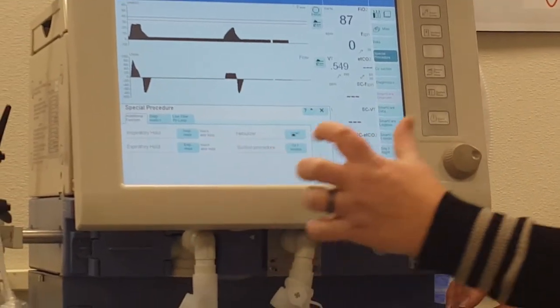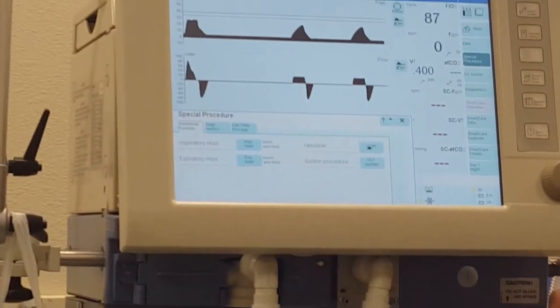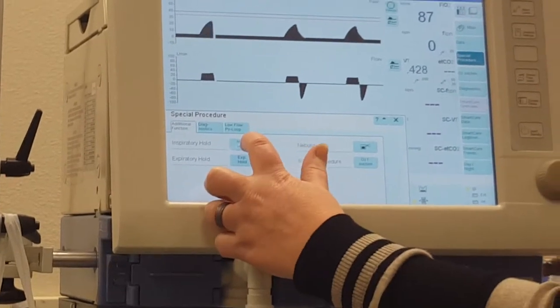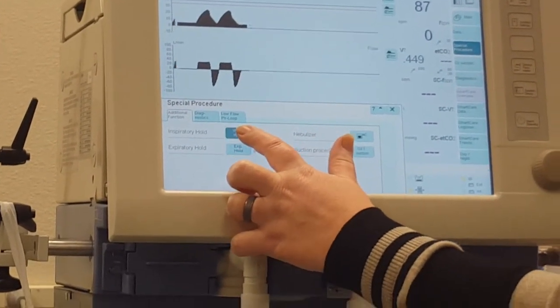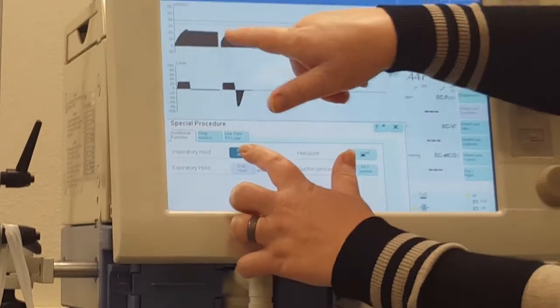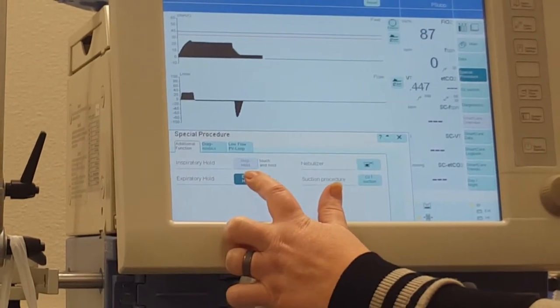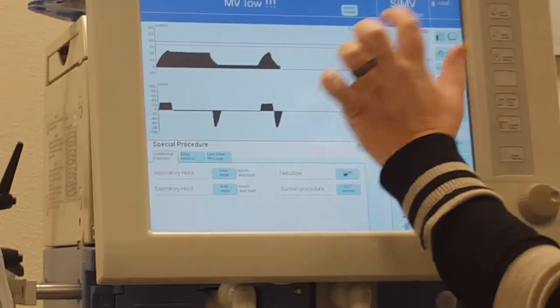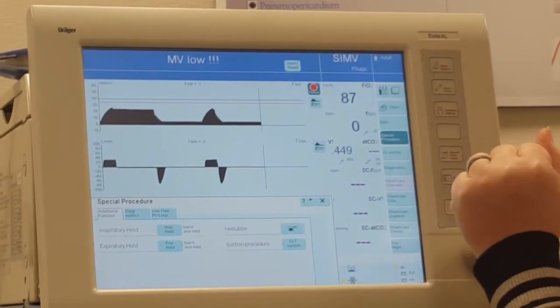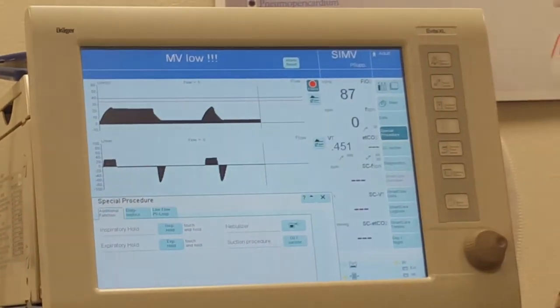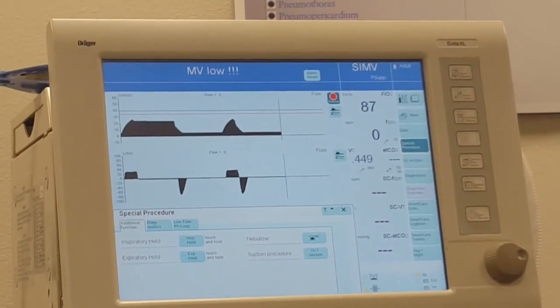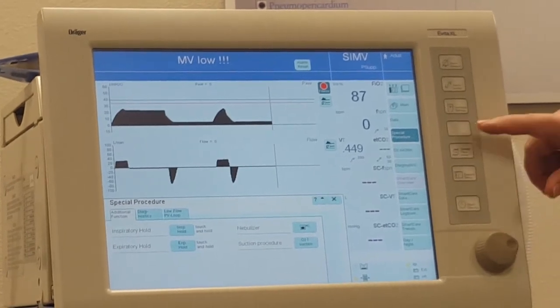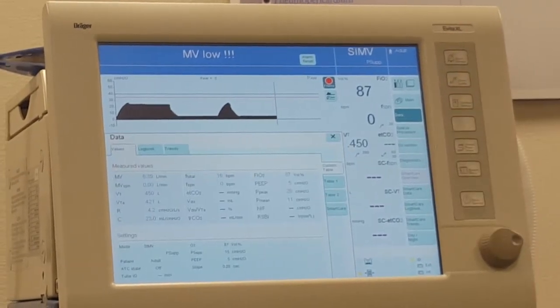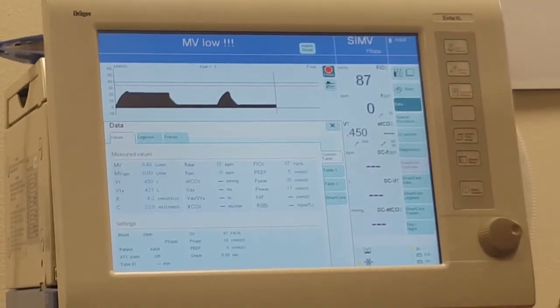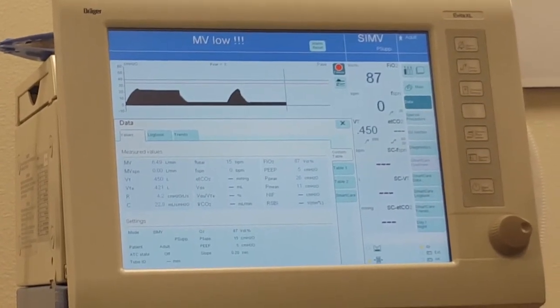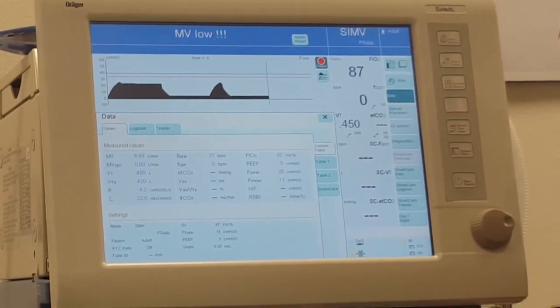Inspiratory hold and expiratory hold, those are the ones we did like on the servo. I want to be able to get my plateaus and my numbers. So I'm going to do inspiratory hold, and it tells you you need to touch and hold it. So now you're going to see the plateau there, and then the expiratory hold, and then I want you to hit the word freeze on the screen. And it's going to freeze your data. The reason you have to do this is because it doesn't always show under the data tab here. Let's see if it's telling right now. It doesn't always show me my plateau. Oh, it's not even listed.